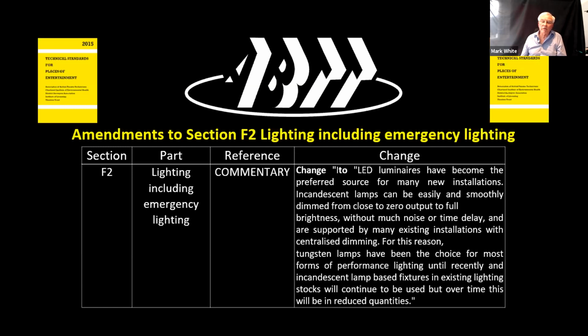There'll always be some method, and they have to be illuminated for something like 3 hours and provide good illumination to do that—that's why we had quite complex emergency lighting systems. The advantage of those, of course, was that it was immediately obvious if any lamps were out, and it was a relatively simple way of testing the whole thing by simply turning off the normal mains and seeing for how long and how bright the escape paths were within the building.